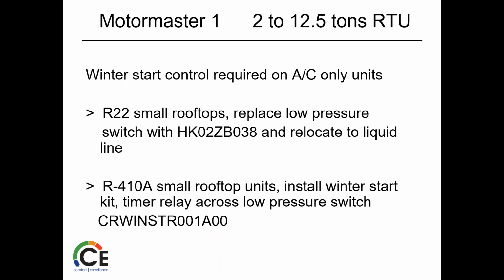So winter start control required again. That's just that delay. It's also what bypasses your low pressure switch, because obviously in colder ambient temps, we're not going to have the right pressures for operation. R22 small rooftops, we're going to replace the low pressure switch. 410A, for the most part, you're just going to run this parallel.